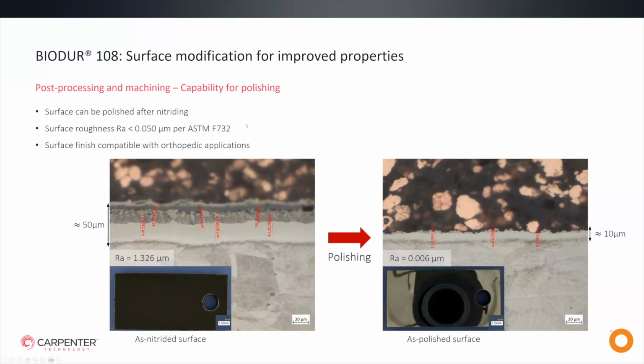So the patent that we provided, right, the approach that we took combines nitriding with controlled polishing and machining, really so that we could ensure the nitriding layer remains compressive and it doesn't introduce harmful tensile stresses, areas that are inconsistent in the surface that could potentially drive cracking. So, we've done extensive testing, including some of the ASTM F732 wear evaluations and fatigue assessments that show that cold worked BioDur 108 and nitriding maintains that mechanical integrity while delivering greater than 50% wear reduction compared to some of the alternatives. And again, I would encourage you to check this out in the patent. So in short, when it's applied properly, when it's applied correctly, nitriding enhances surface performance without undermining the base material's capability for toughness and performance.